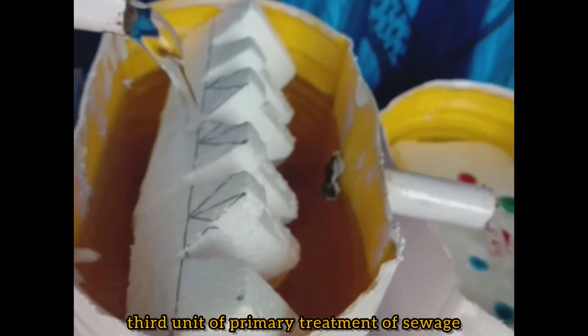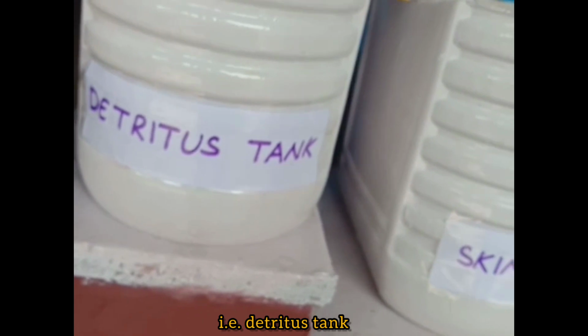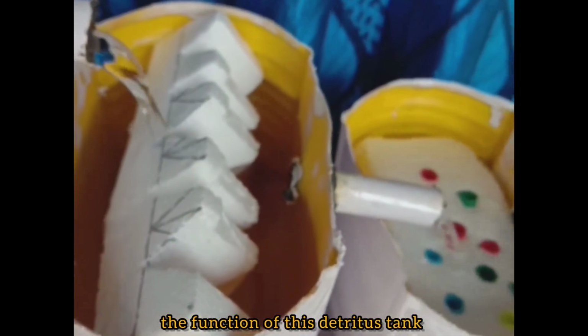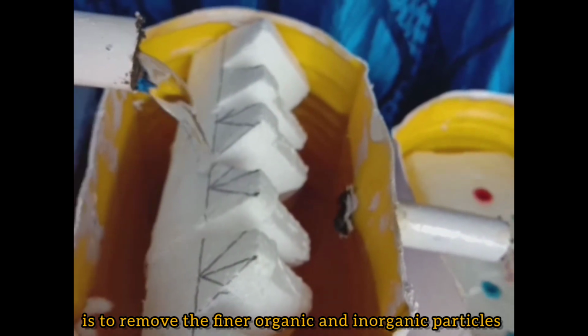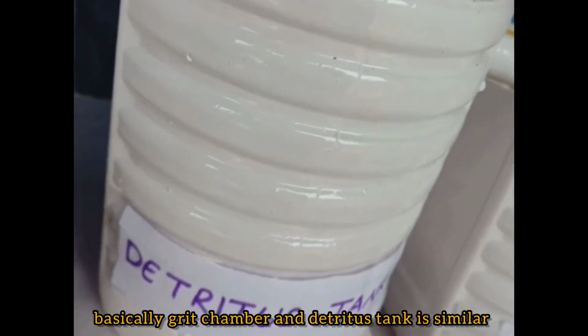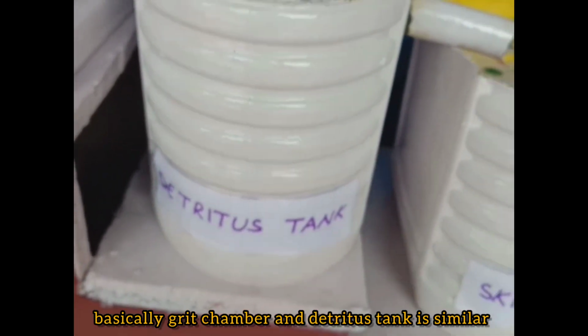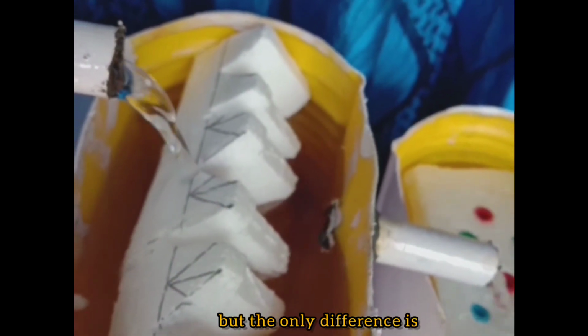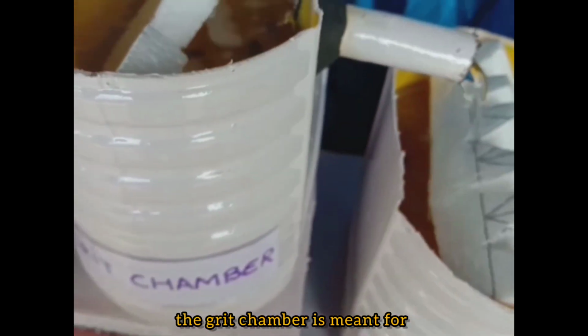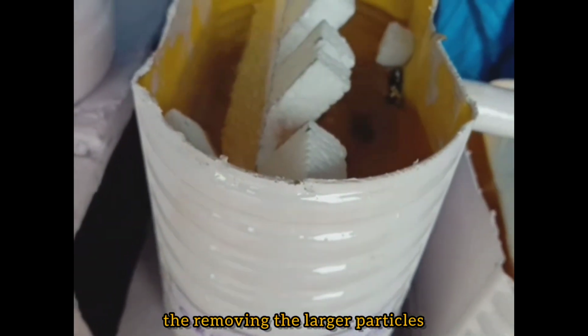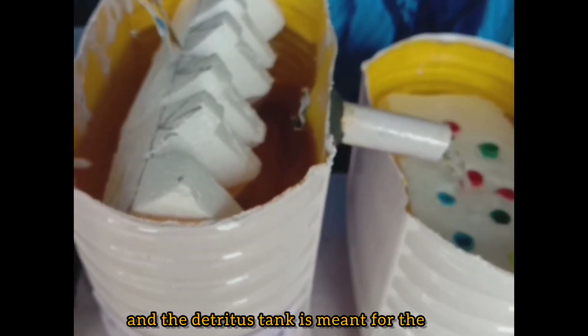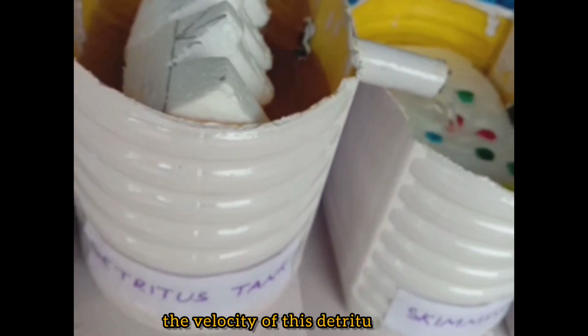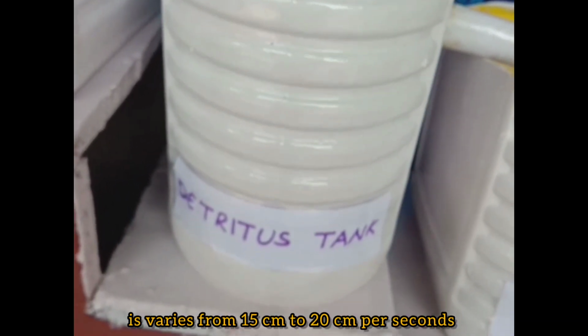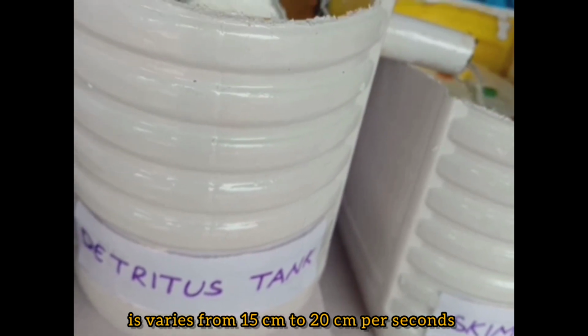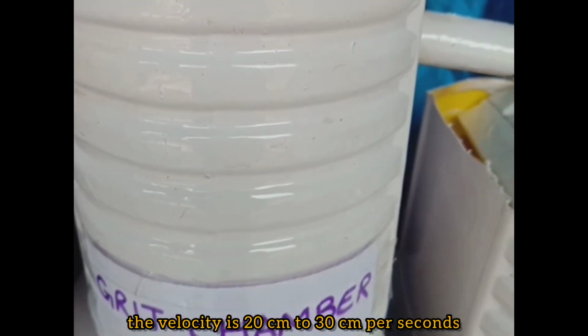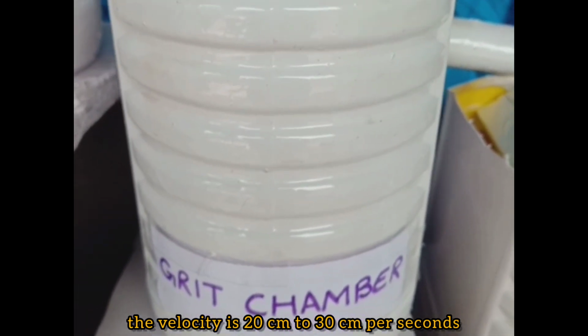The third unit of primary treatment of sewage is the detritus tank. The function of this detritus tank is to remove the finer organic and inorganic particles. Basically, the grit chamber and the detritus tank are similar, but the only difference is that the grit chamber is meant for removing the larger particles and the detritus tank is meant for removing the finer particles. The velocity in this detritus tank varies from 15 cm to 20 cm per second, whereas in the grit chamber the velocity is 20 cm to 30 cm per second.